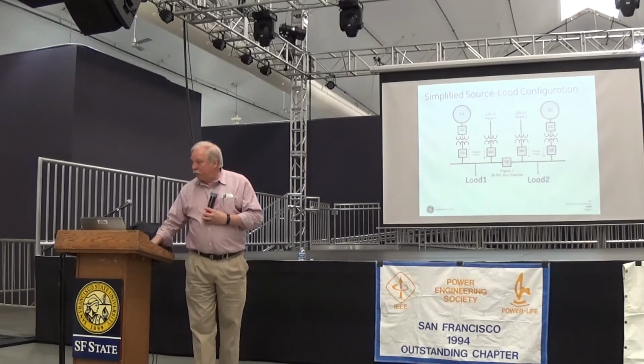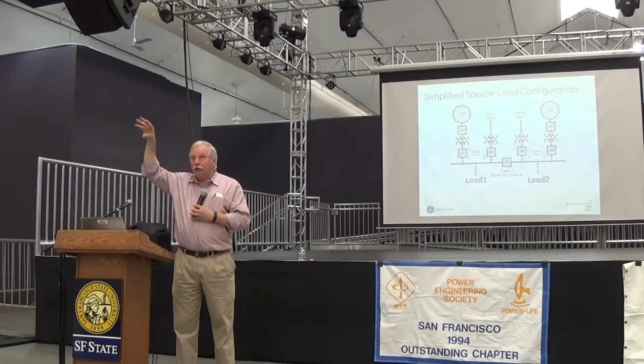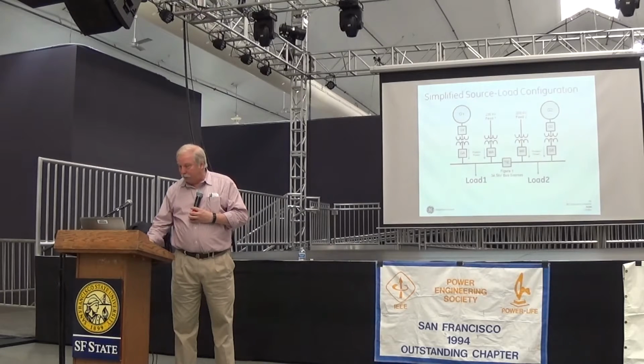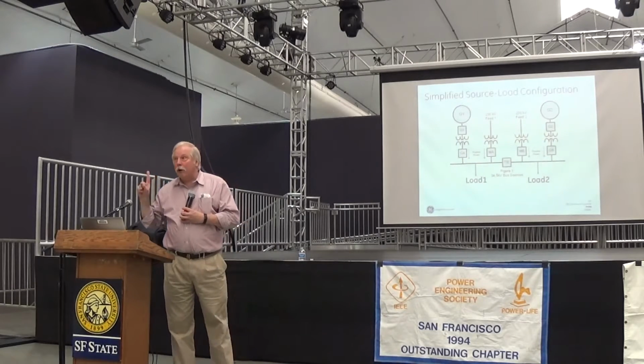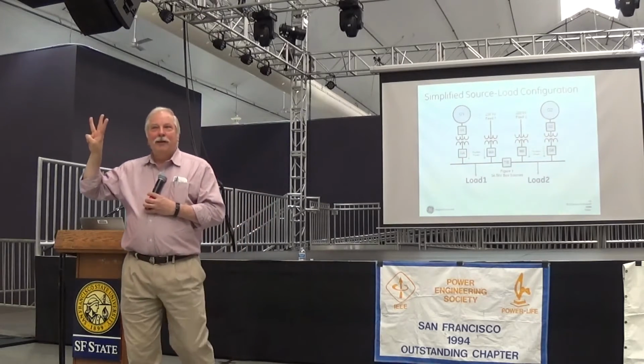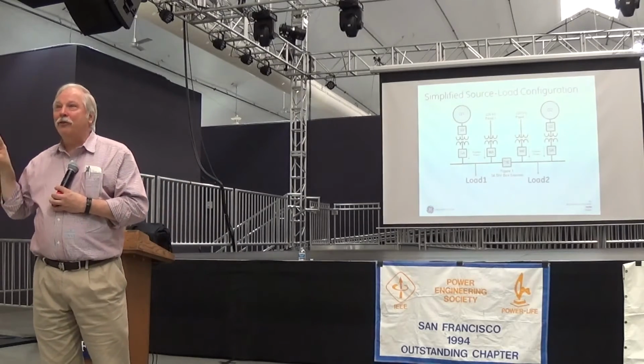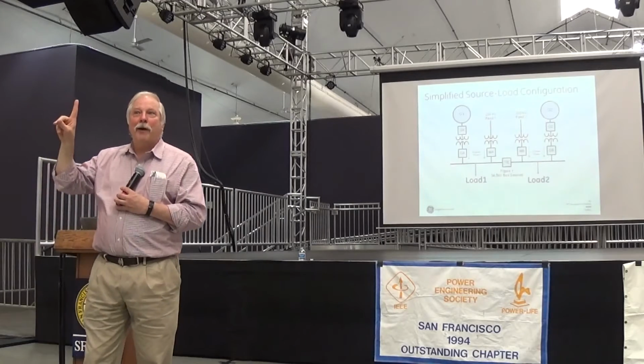This is an actual scenario from an industrial. This particular industrial has 2 internal gas turbines, each one at 47 MVA, and it has 2 230 kV feeds coming in to 2 transformers. Any single transformer can run the entire plant, but guess what's happened 3 times? As I mentioned, they've lost the two 230 feeds, and they had 1 unit out for repair.